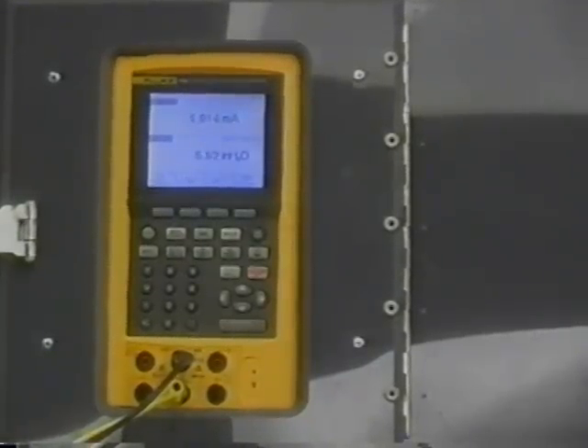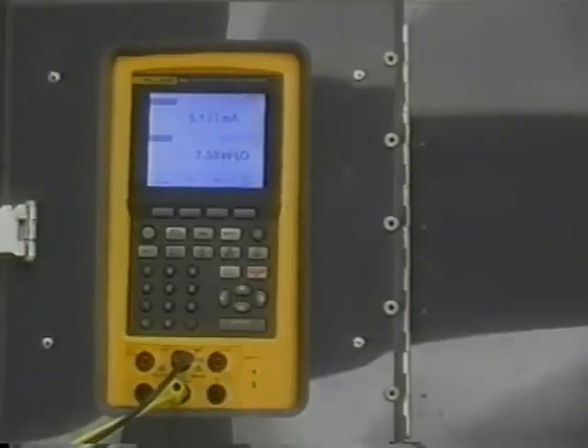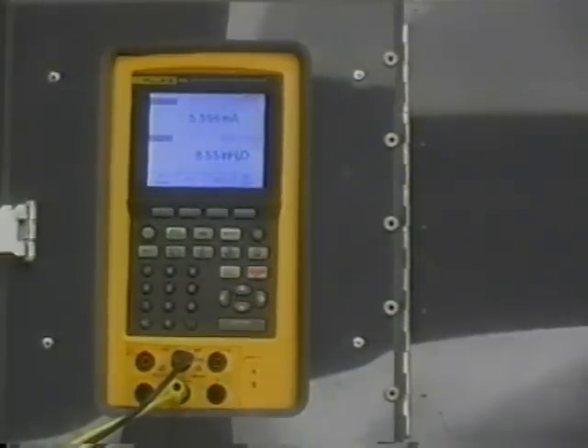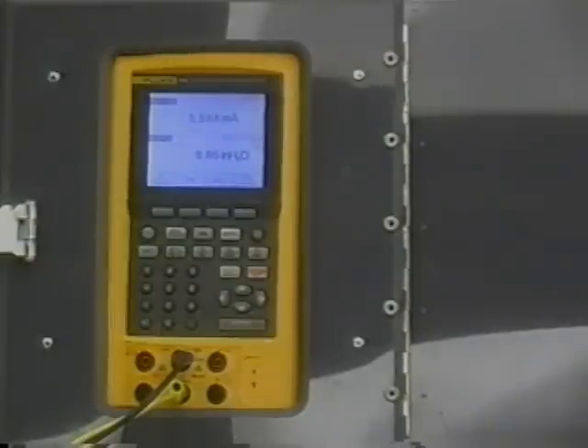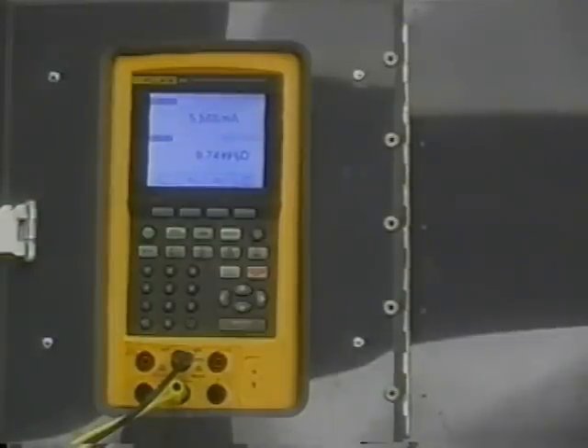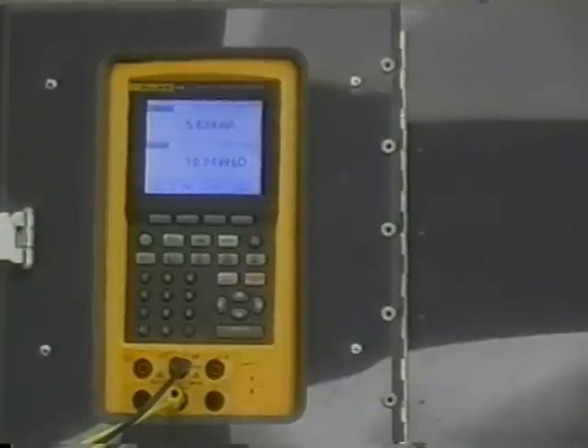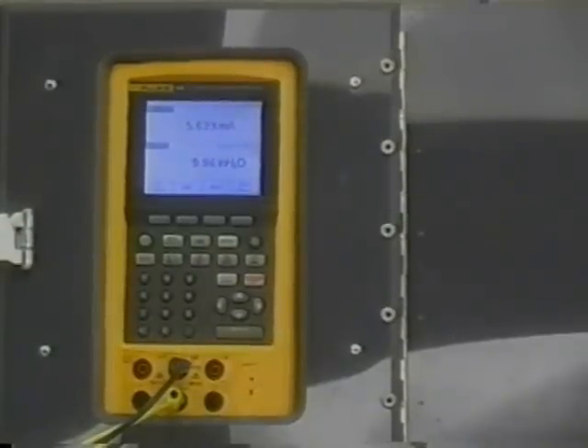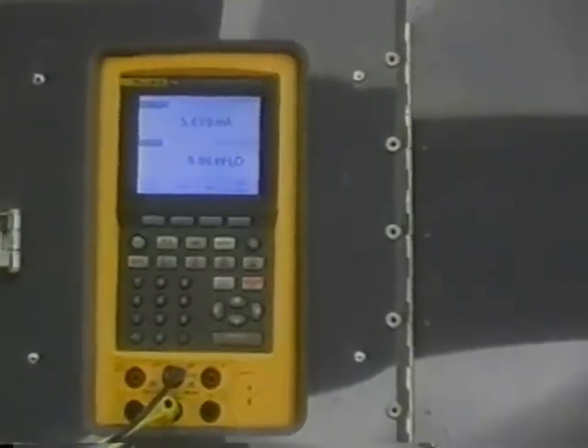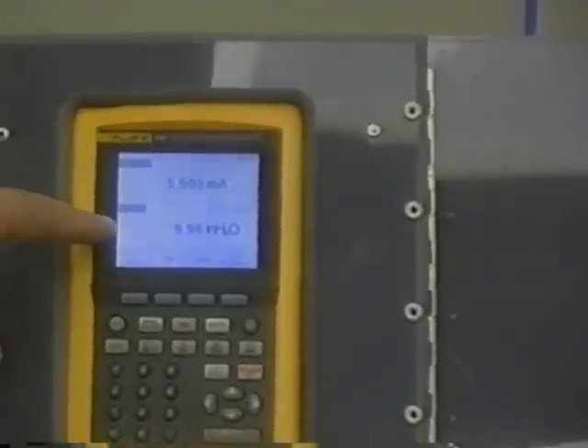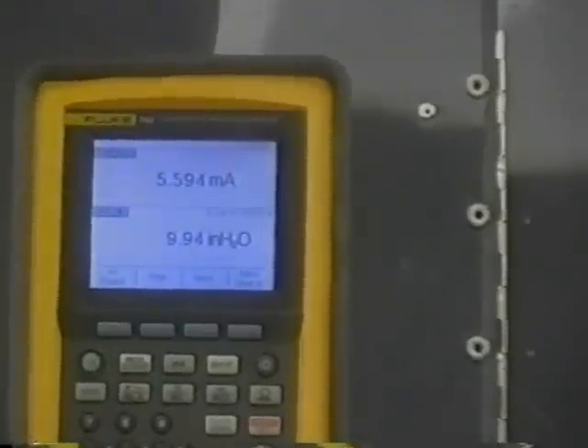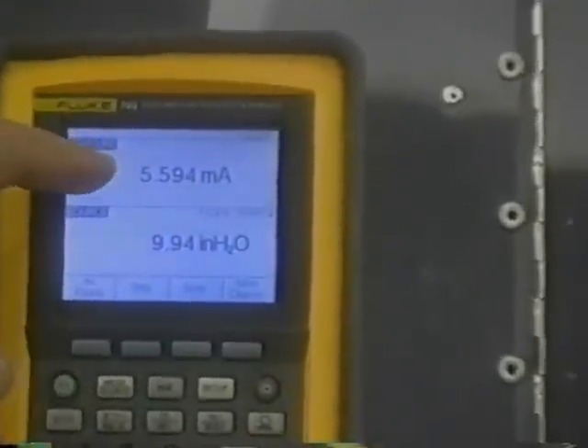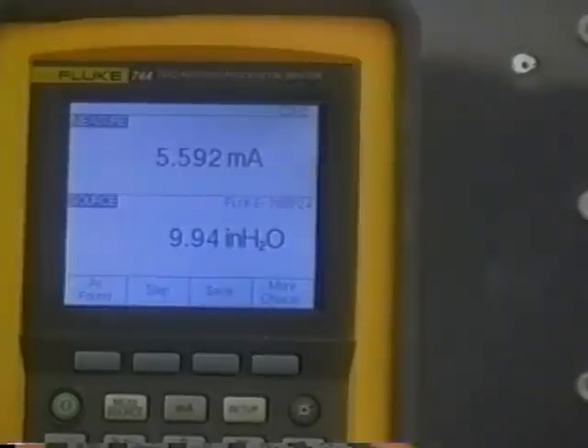We usually go up scale by 10% increments, so if I dial this up to 10 inches of water, that'll represent 10% of the 0 to 100 inch water range. It's not too critical to get it perfect because an inch of water is a very small pressure unit. Close enough. We have 9.96 inches of water and 5.59 milliamps.